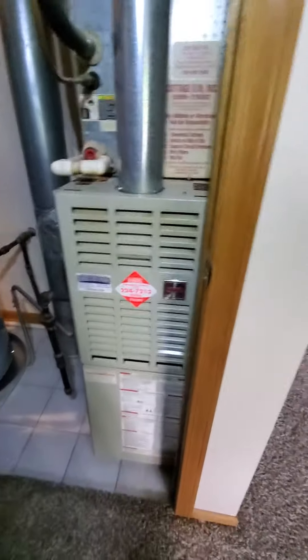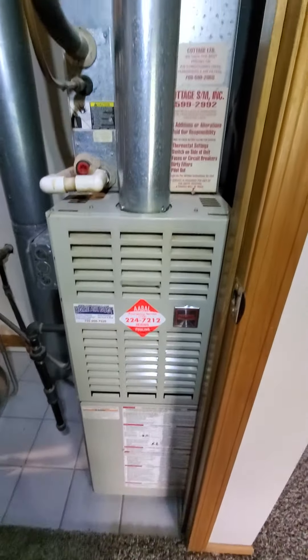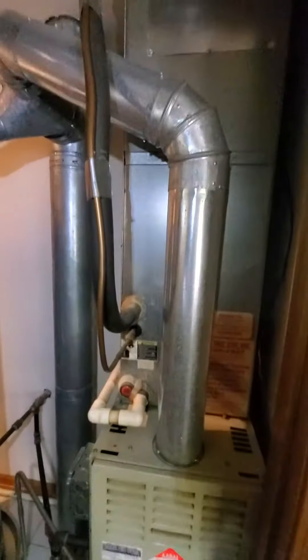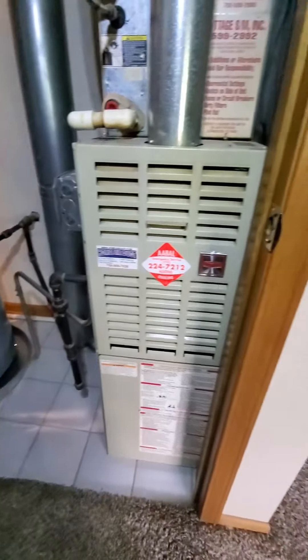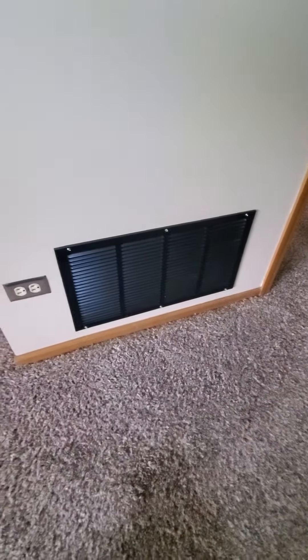Hello, Chelsea's Tech 874. We're out in Oak Forest, homeowner's looking to get a full system here. Existing is an 80% efficiency at 63,000 BTUs. We are in a condo setup, on the second floor. Supply coming in at about 20 by 13, existing filter inside at 16x25 by one, and your return air is going through right about here. Kind of get an idea of your workspace.